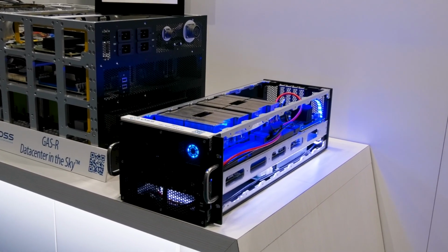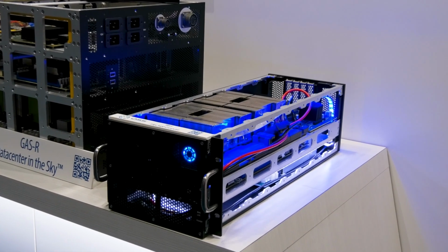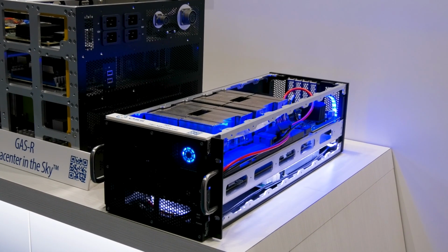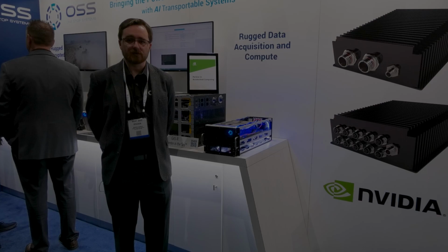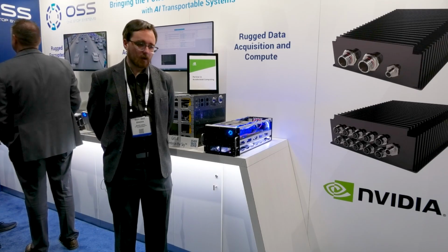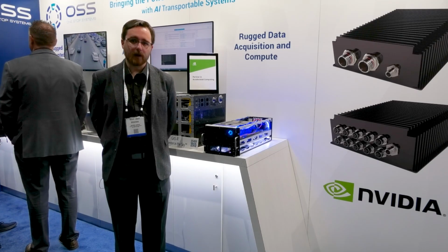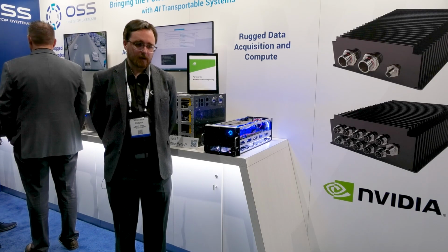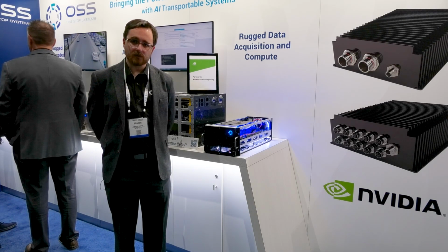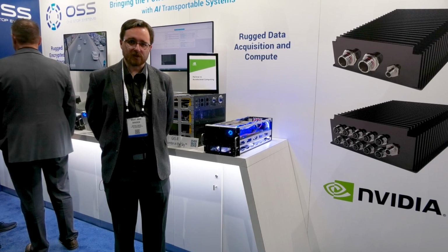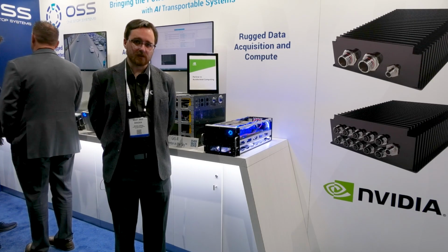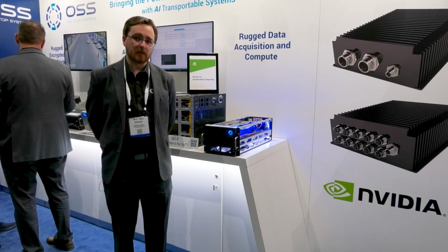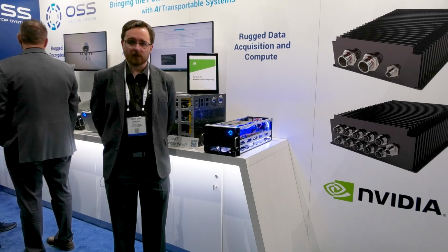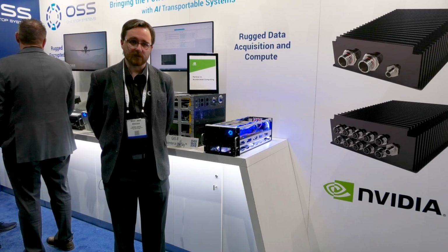The Rigel platform as we have it today is an air-cooled platform designed to support temperatures of up to around 30 degrees Celsius at full performance, which is a 2.5 kilowatt heat load. When you bring this application into higher ambient temperatures, say 50 C, you can limit the power of the GPUs using internal commands, which limits not only the input power of the system but extends the operating ambient temperature you can run the system at while maintaining full performance.